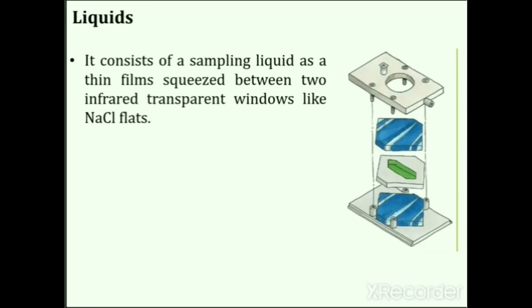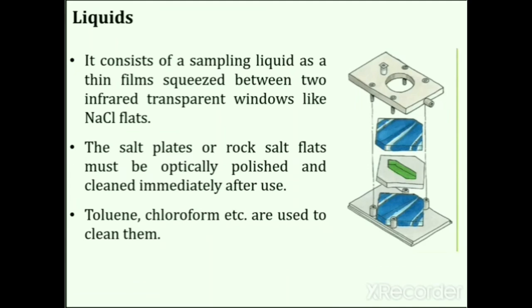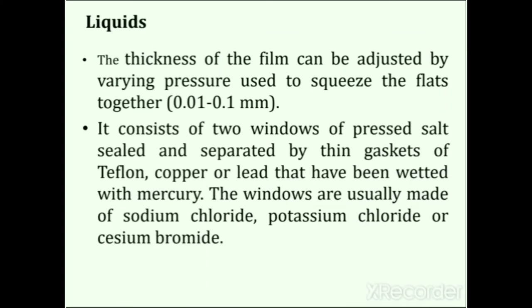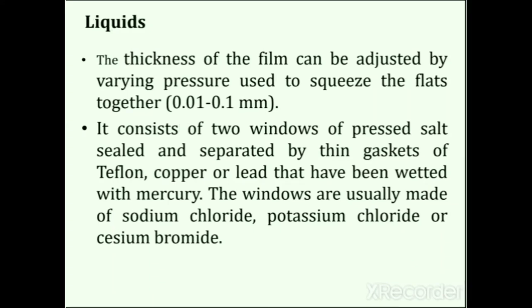Liquid samples are analyzed by making a thin film squeezed between two infrared transparent windows like NaCl flats. The salt plates must be optically polished and cleaned using toluene, chloroform, etc., kept dry and handled only by their edges. Thickness of the film can vary between 0.01 to 0.1 mm. The cell consists of two pressed salt windows sealed and separated by thin gaskets of Teflon, copper or lead wetted with mercury. A first cell contains the sample and a second cell containing pure solvent is placed in the reference beam, so solvent absorption is cancelled out and the spectrum recorded is that of the solute alone.